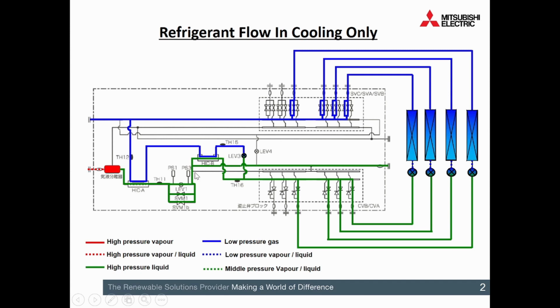These two pressure transducers here, I'm not actually using those when it looks at the cooling side of things. I use those for heating. And we can get an idea of how well that subcooler is working by looking at TH15 and TH12 as well. So I'll say I've got a nice subcooled liquid passing off to the actual indoor units.